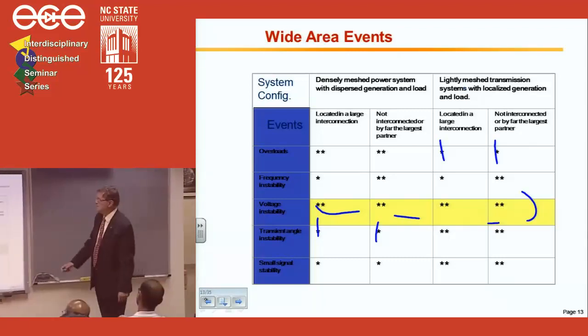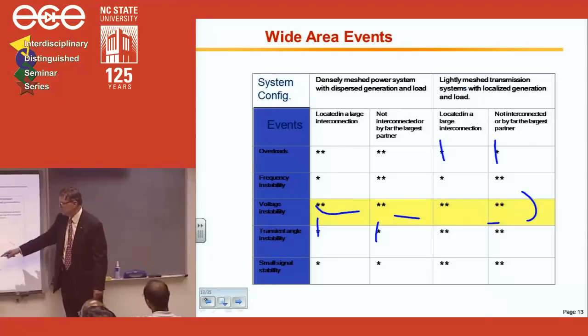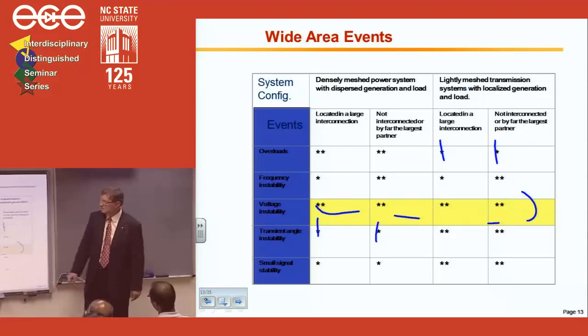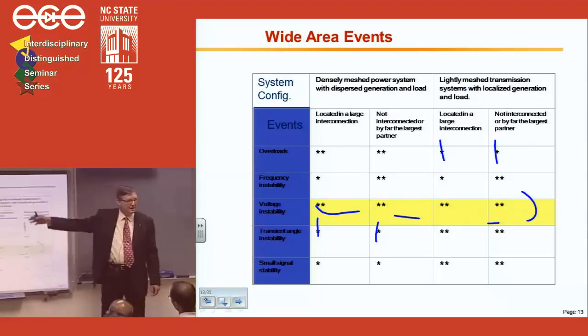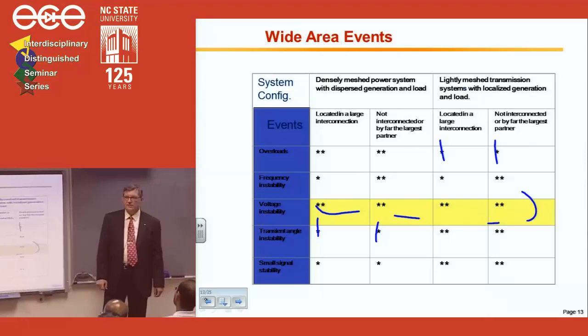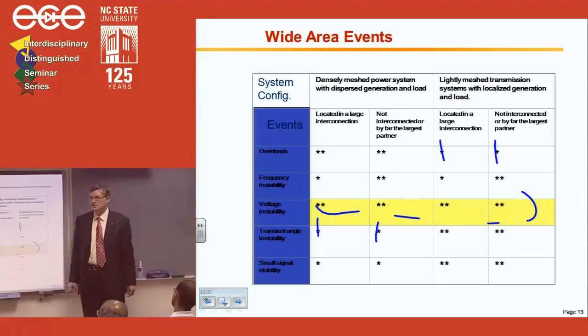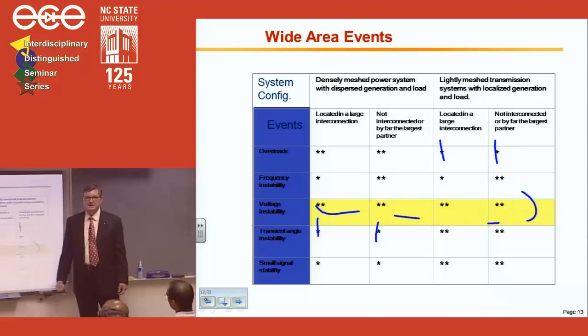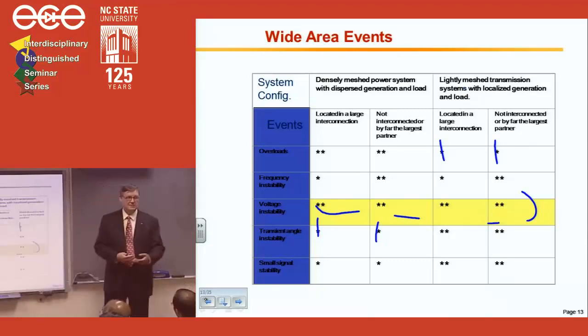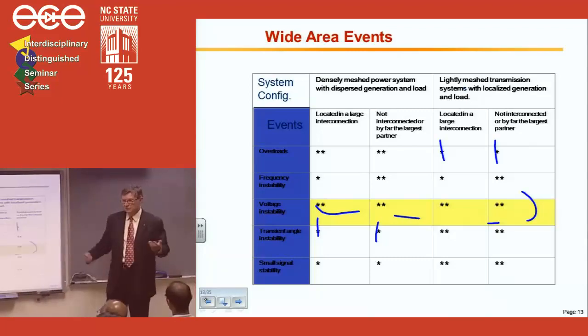In a lightly meshed transmission network, you still have more transient stability problems, while in a densely meshed network, you may have a bit more overload problems. But it's all happening, and you cannot distinguish what caused the blackout or which of these events. Very often all these happen at the same time.